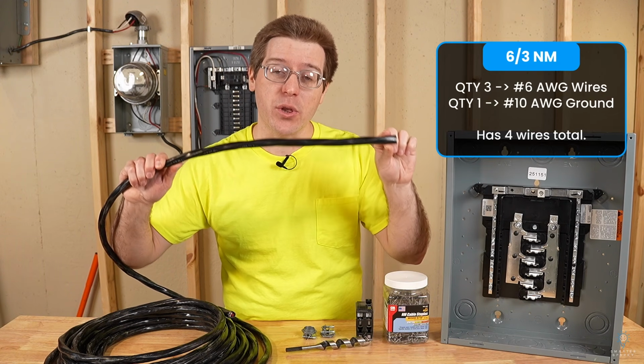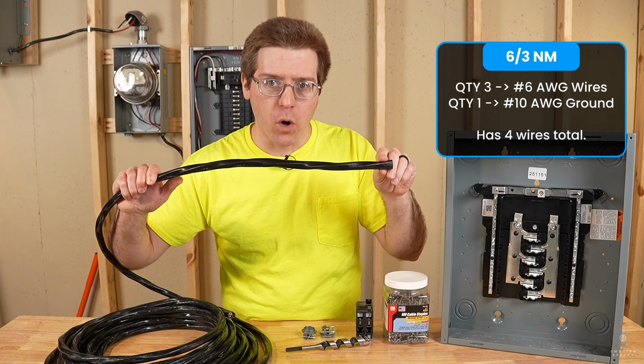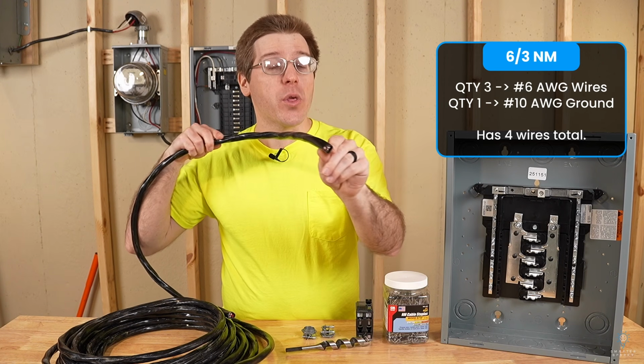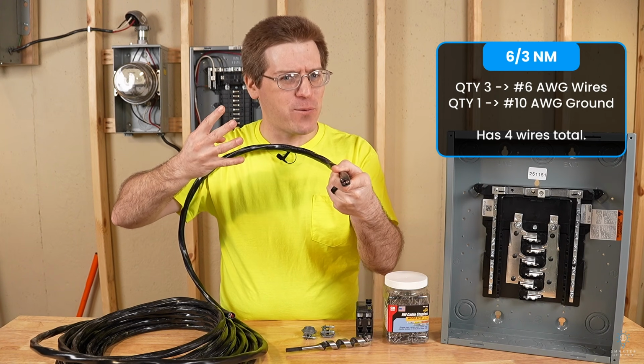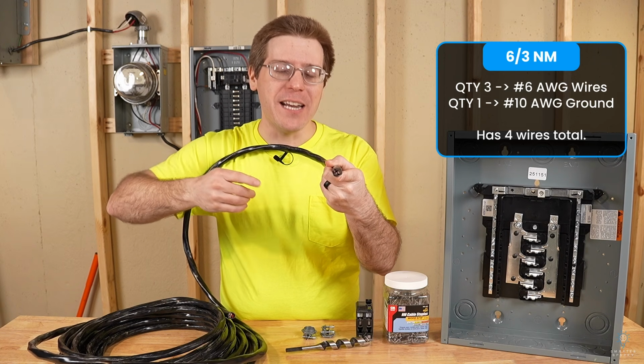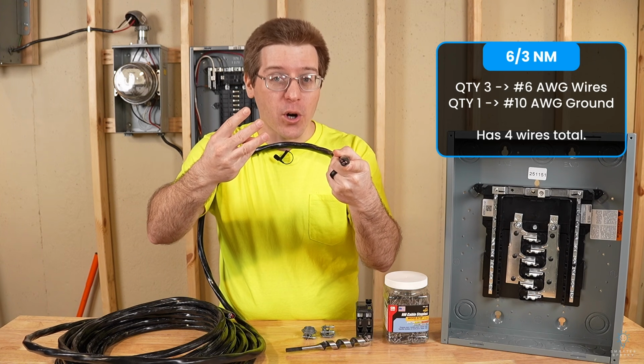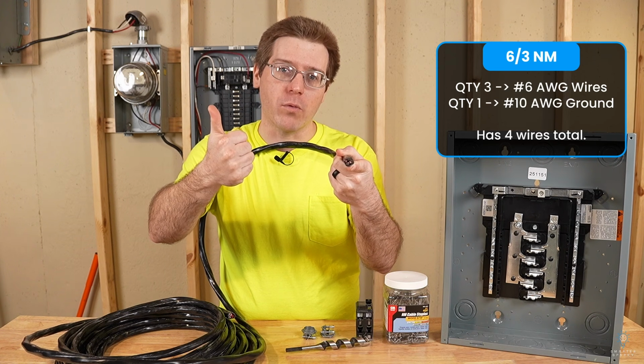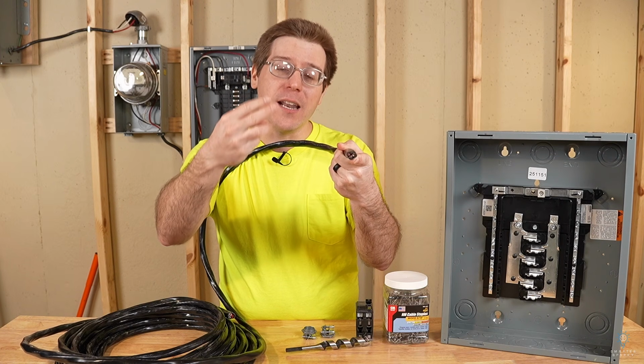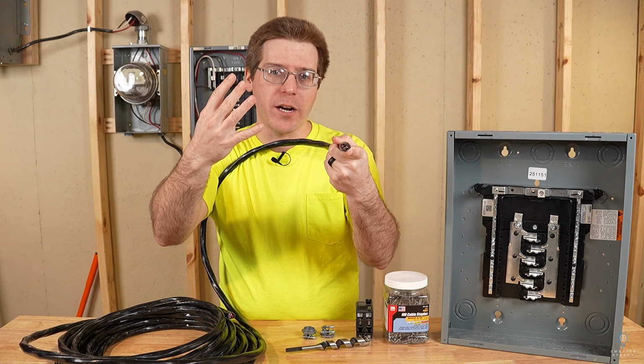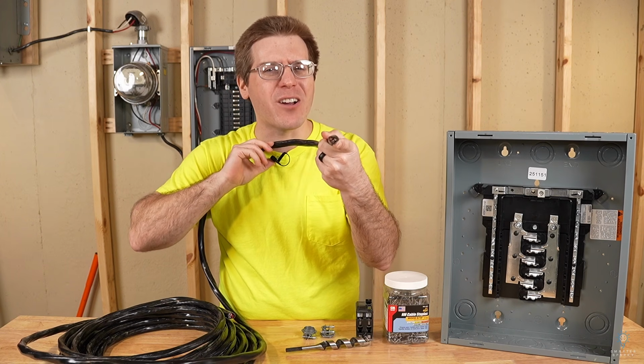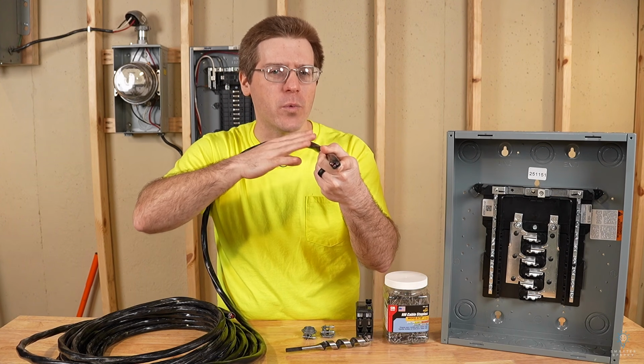This is 6/3 NM wire, or Romex. 6 gauge and 3 wires actually means it has 4 wires, because that makes sense, right? It's actually got 3 wires for current carrying capabilities and 1 ground. So it's got a black, a red, a white, and then a ground wire in it. So 4 wires total, but they call it 6/3. They don't count the ground wire.